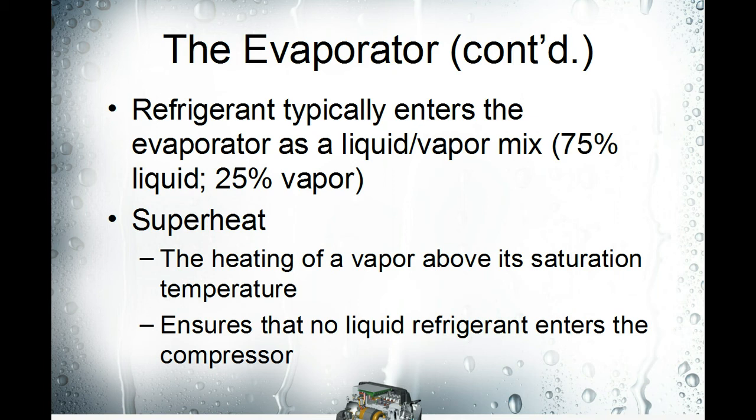That change of state is what happens through most of the evaporator. Near the end of the evaporator, the vapor becomes superheated and rises above the saturation temperature. The reason we have superheat is to make sure that we have no liquid refrigerant going back to the compressor, because that's what damages valve plates and burns up compressors.